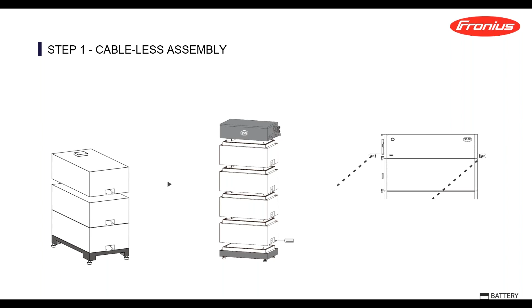And now we go into the installation itself. It has 3 really simple steps. The first one is putting all the modules together. This is a cable-less installation, so you just need to clip the modules on top of each other, and with just one screw, you can lock them together. Very important, attach them to the wall, because especially in the case of a large HVM, 22 kilowatt hours, it's a very large tower, so it is very important to attach it to the wall.